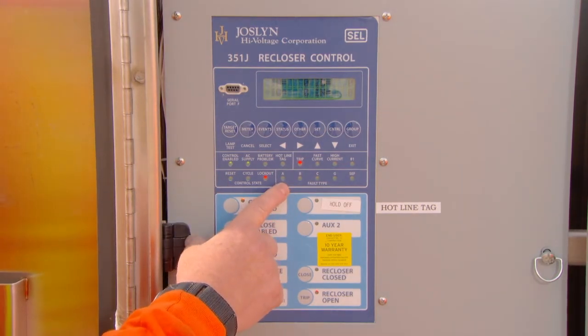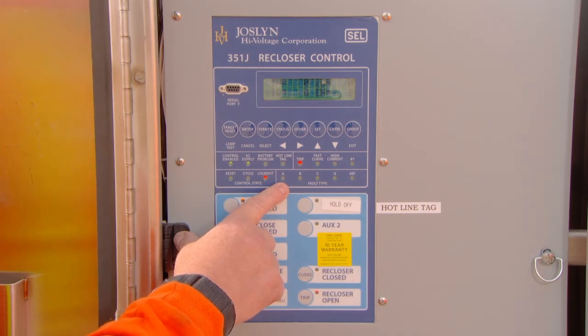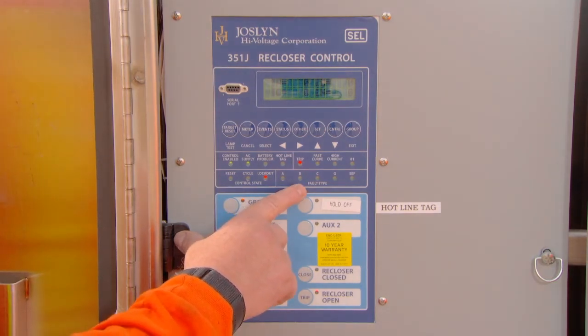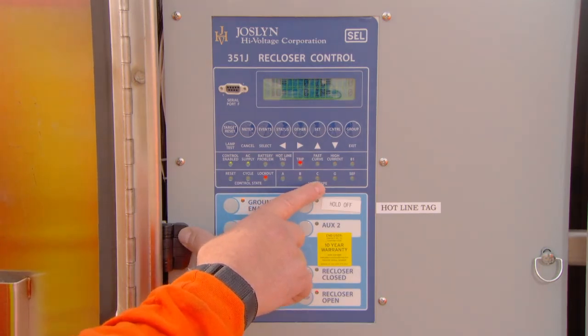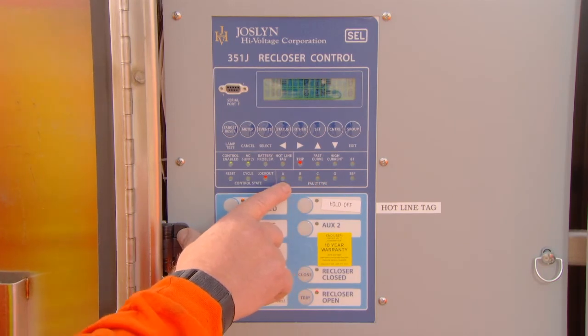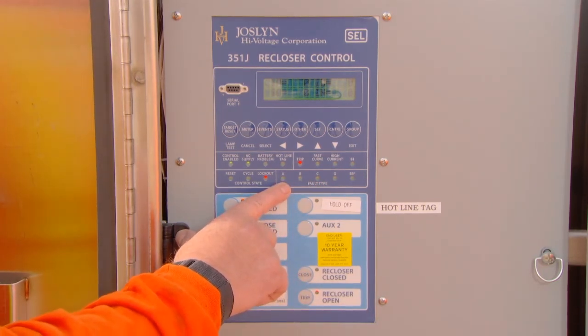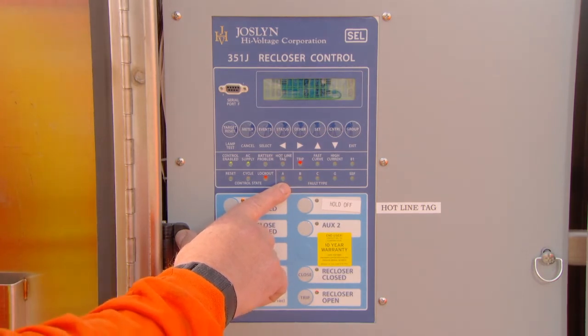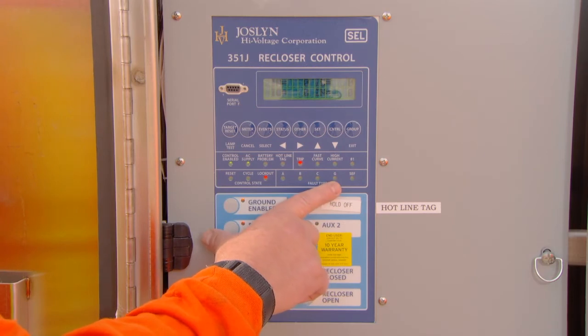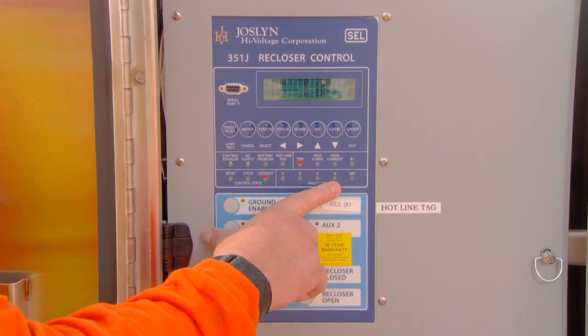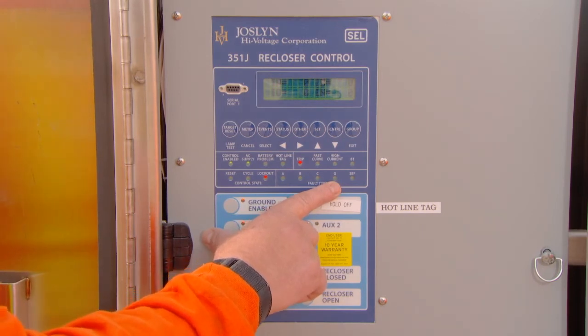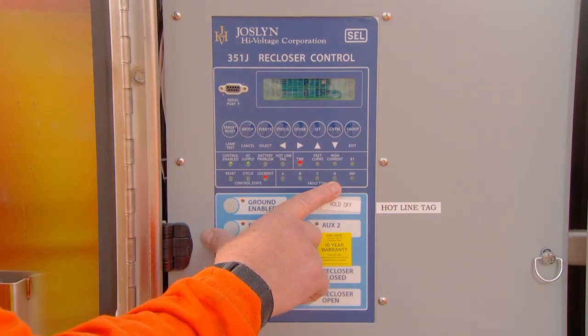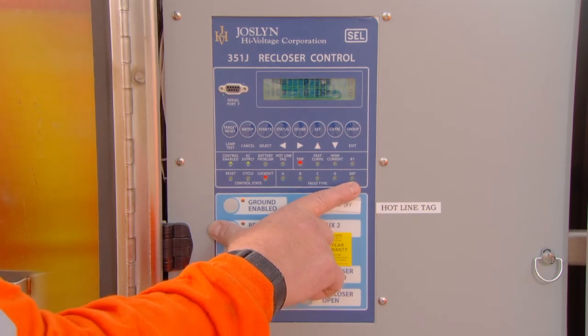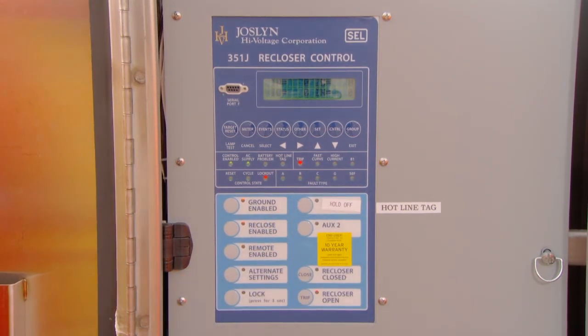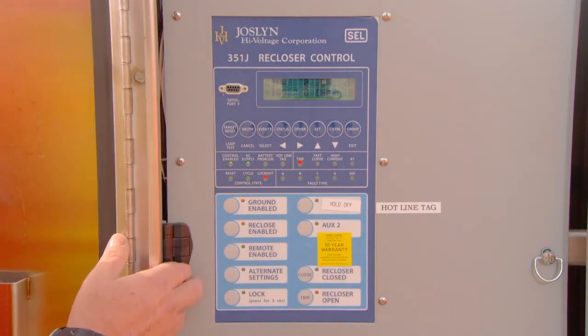The next three status indicators are the A, B, and C phase fault current indicator LEDs. These indicators will illuminate to indicate on which actual phase or phases the fault occurred. Next is the ground LED. There is no ground on the VBM44 recloser, so this picks up any imbalance between the phases. If there is a significant imbalance that meets the threshold setting in the control, that light will also activate. Finally, we have the SEF, or Sensitive Earth Fault Indicator LED. This feature is not used in this control panel.